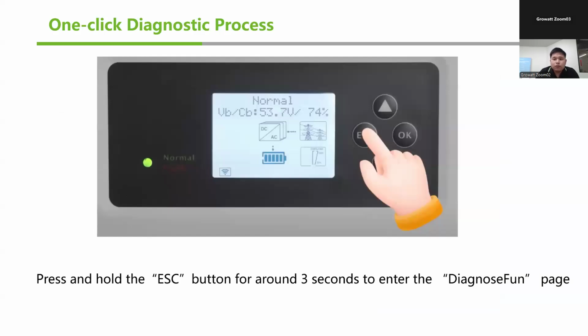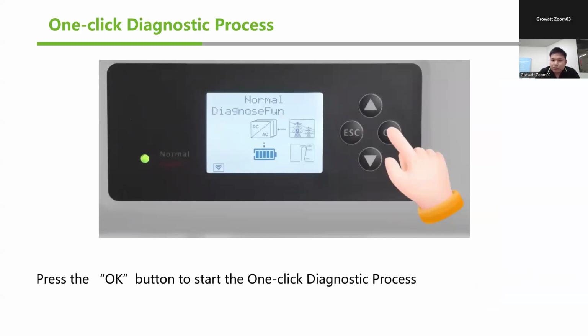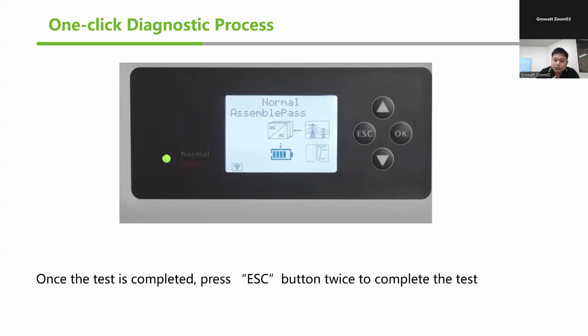So to start this process, it's very simple. Not only the installer can check, but also the end user, because all you have to do is go to the inverter and then press on the user interface. So let's say if I am the user and I just want to check if my inverter is working well, just want to check the health. I can go to the inverter and just hold the escape button for more than 3 seconds. It's going to enter the diagnose fun page. Fun doesn't mean having fun, it actually means function. So the diagnose function page, and then press OK. It will start the process. And then it's going to go through all the 5 processes that I was speaking about earlier. And once everything has been checked and done, if everything is working okay, the inverter will show as normal, assemble passed. So once this is done, just press escape twice and complete the test.